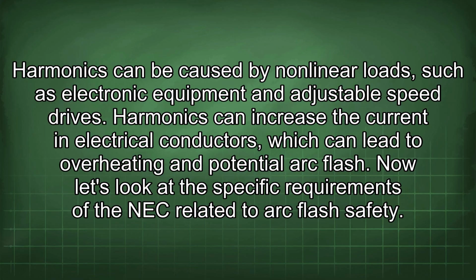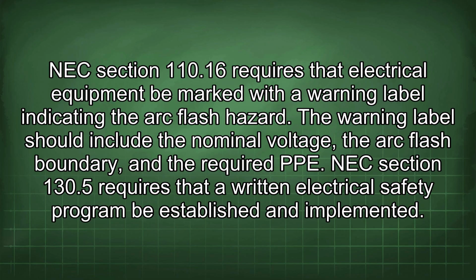Now let's look at the specific requirements of the NEC related to arc flash safety. NEC section 110.16 requires that electrical equipment be marked with a warning label indicating the arc flash hazard. The warning label should include the nominal voltage, the arc flash boundary, and the required PPE.